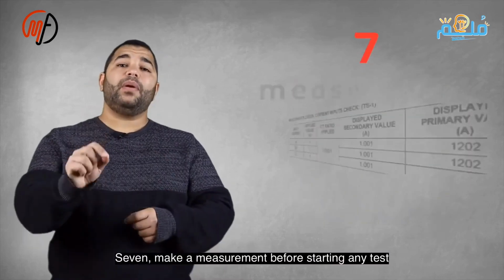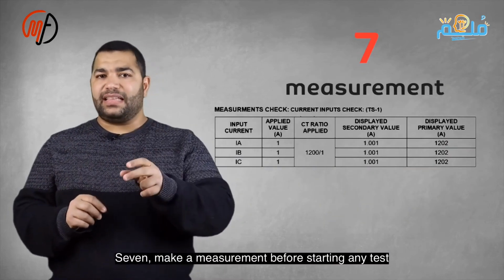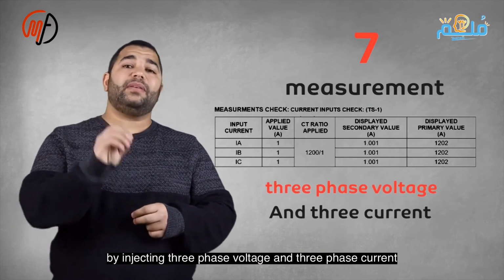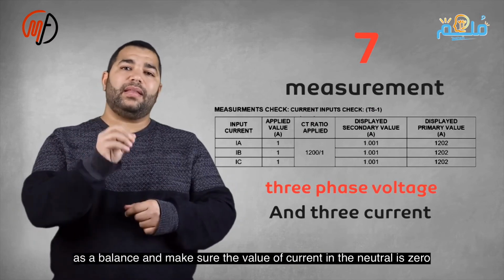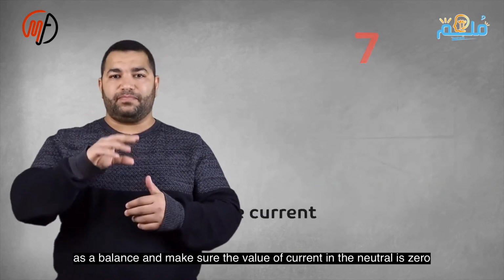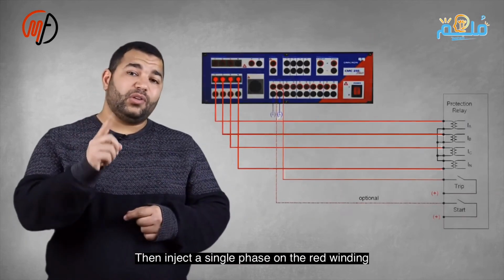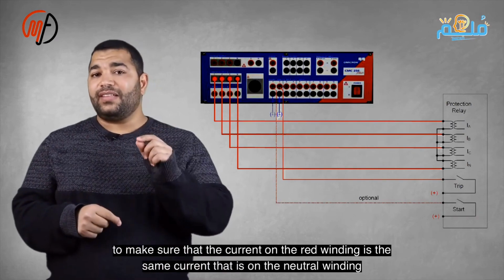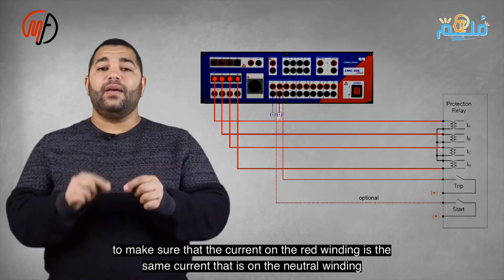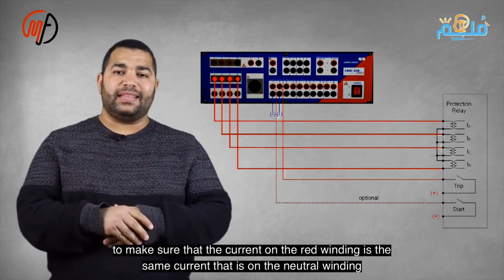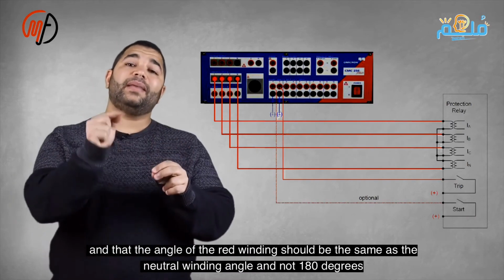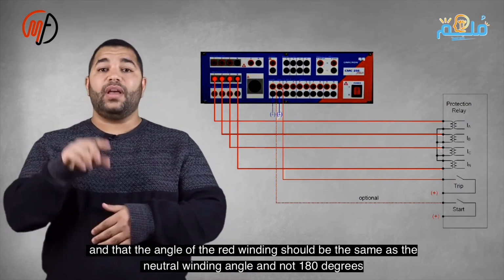Seventh, perform a measurement before starting any test by injecting three-phase voltage and three-phase current as a balance, ensuring that the current value in the neutral is 0. Then, inject single phase on the red winding to confirm that the current on the red winding is the same as the current on the neutral winding, and that the angle of the red winding should be the same as the angle of the neutral winding, not 180 degrees.